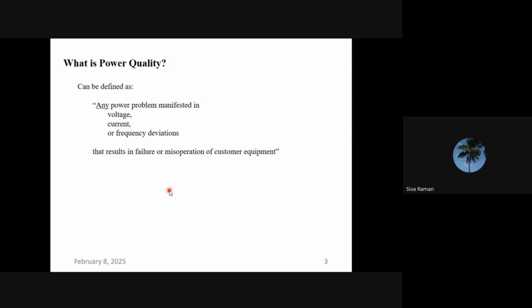important concerns for an electrical system, especially the AC system. So generally, power quality can be defined as any problems in voltage, current, and frequency deviations. Any deviation from the ideal characteristics of the voltage, current, and frequency is generally called a power quality problem. This problem will result in failure, mal-operation, increased energy loss, premature equipment failure, and lifetime reduction. So due to poor power quality, any of these things may happen, like premature failure or mal-operation.